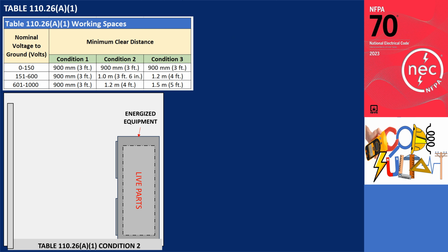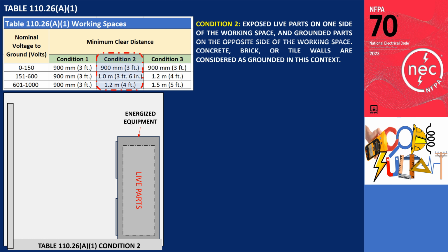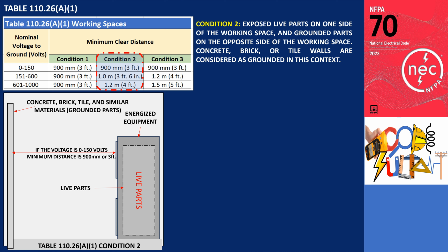The following illustration serves as an example demonstrating compliance with Condition 2. In this scenario, exposed live parts are present on one side of the working space, while grounded parts are situated on the other side. For installations falling under Condition 2, where the voltage ranges from 0 to 150 volts, the minimum required clearance distance is 900 mm or 3 feet.